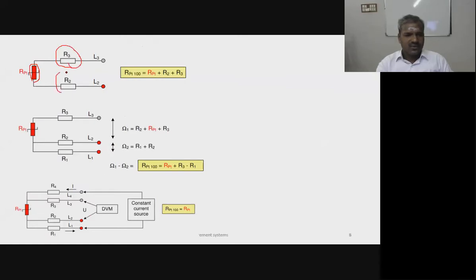The total resistance detected is the platinum element resistance and the lead wires together. Because the lead wire resistance is included in the measurement, it leads to error.